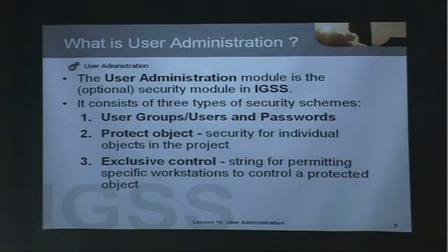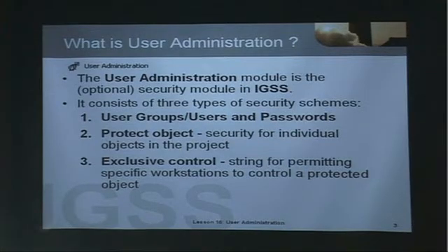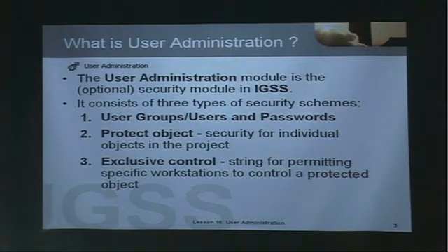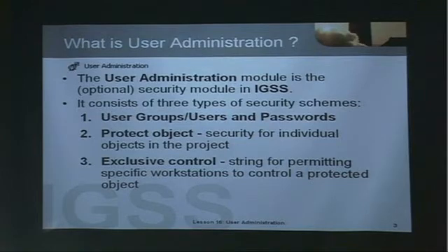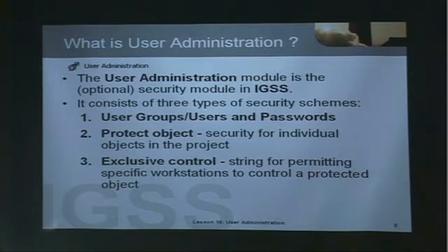What is user administration? The user administration module is the optional security module in IGSS. It consists of three types of security schemes. The first level: user groups, users and passwords. The second level: protect object — security for individual objects in the project or configuration. And the third level: exclusive control — a string configured for permitting specific workstations to control a protected object. In our exercise, we will only cover the first two levels: user groups and the protect object.